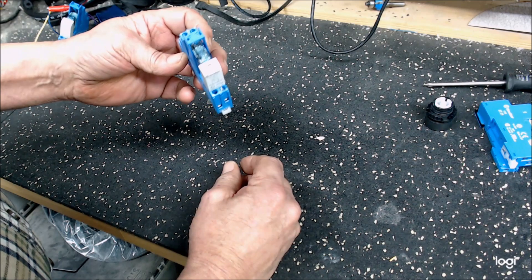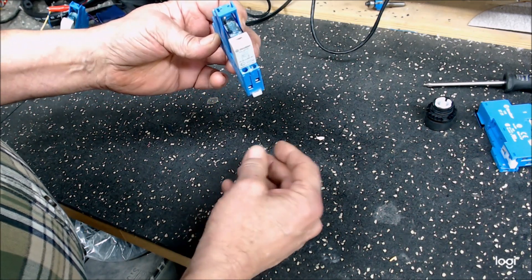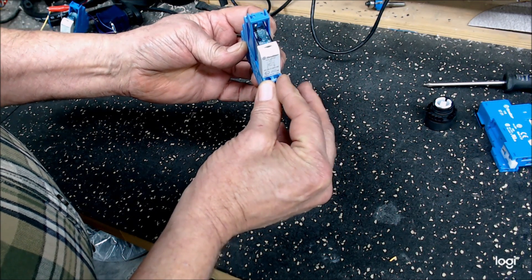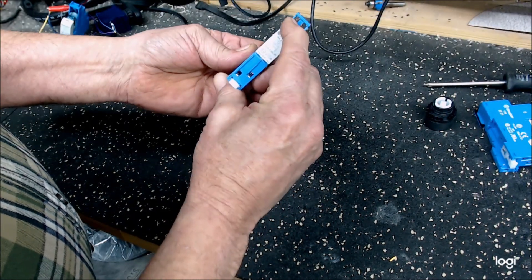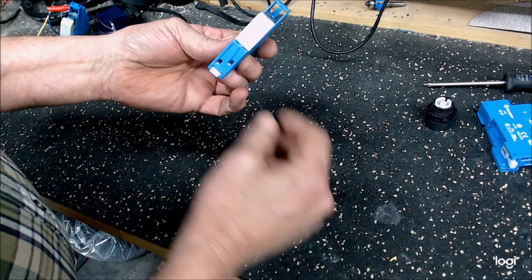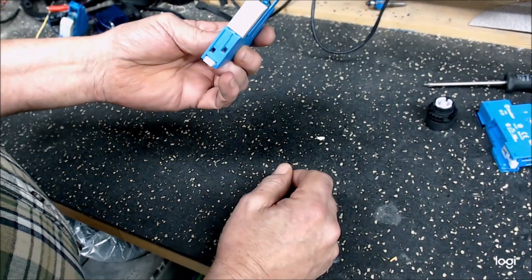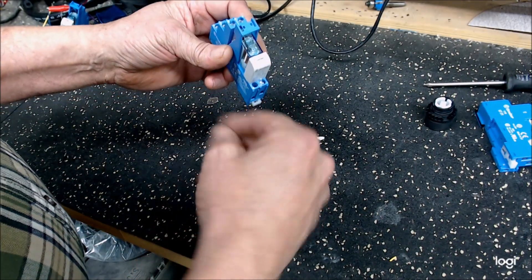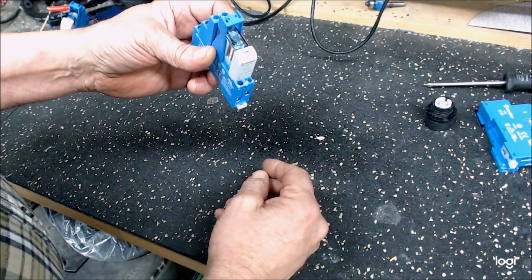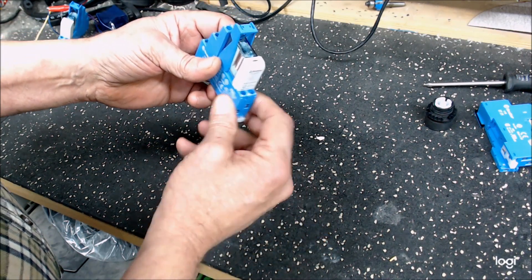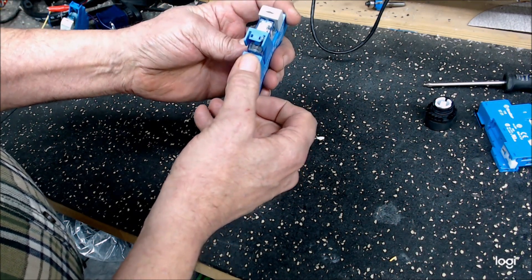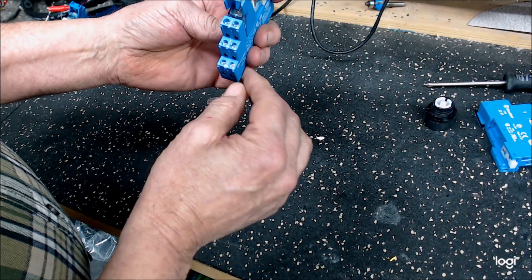Just quickly - you can see that the coil voltage is here, so this is where the coil voltage is applied. This is an LED indicator. It also has snubber and quench arc type features, but it has a green LED so you'll be able to see when the relay is active. Over here on this side are the common, normally open, and normally closed contacts. For this example we're going to use the common and the normally closed.